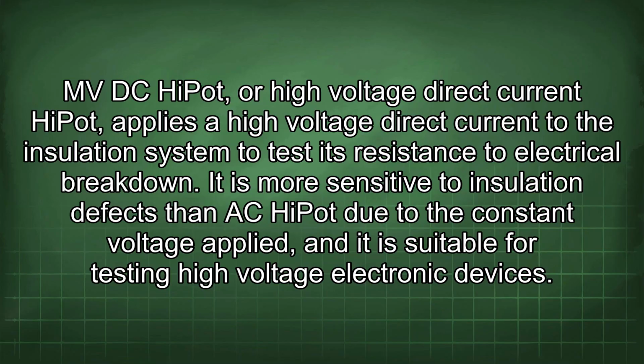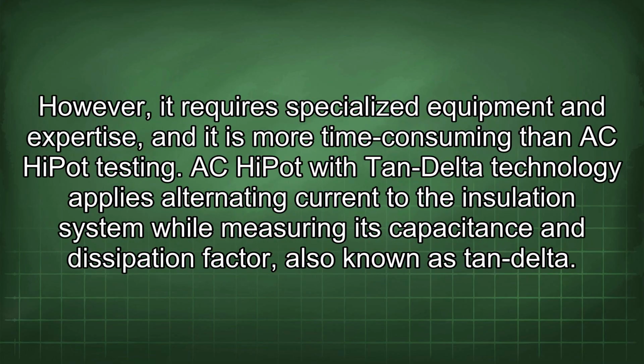MVDC HiPot, or High Voltage Direct Current HiPot, applies a high voltage direct current to the insulation system to test its resistance to electrical breakdown. It is more sensitive to insulation defects than AC HiPot due to the constant voltage applied, and it is suitable for testing high voltage electronic devices. However, it requires specialized equipment and expertise, and it is more time consuming than AC HiPot testing.